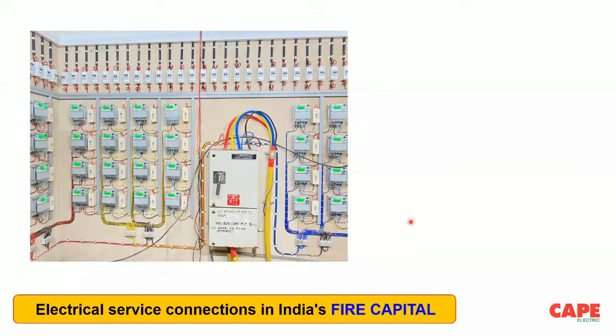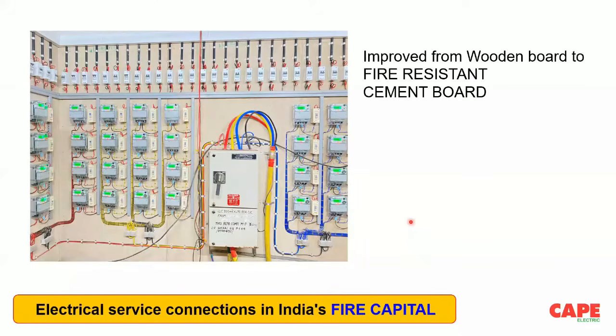So now I will show you a small example. Rather than talking about a big safety scenario, we should always start, or my way is to start, from some small things. I'm just showing you the meter board from Bombay, which is used in most of the apartments. There is a meter room, and all the meters and the protective devices are mounted on the wall. The first point to note is that earlier it was a wooden board which was catching fire quite often, but nowadays the wooden board is stopped and fire-resistant cement boards are used. Anyway, congratulations, it's a good thing because the chance of fire on wood is avoided, but still a lot of existing buildings have wooden boards.